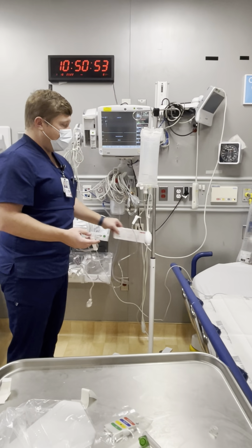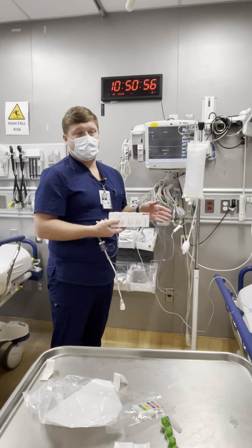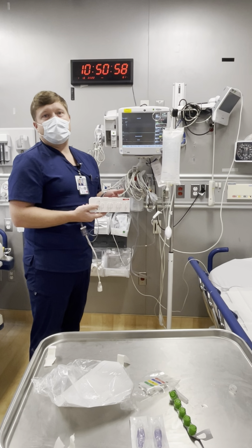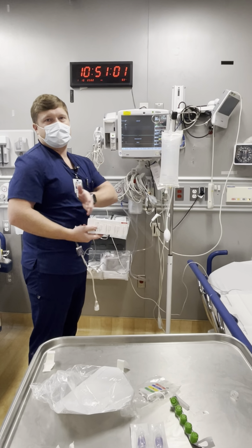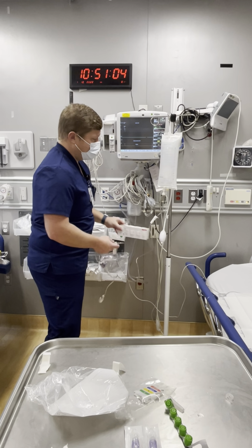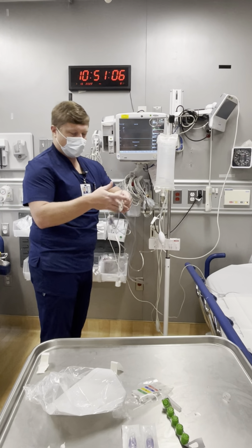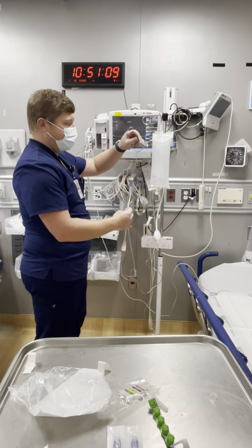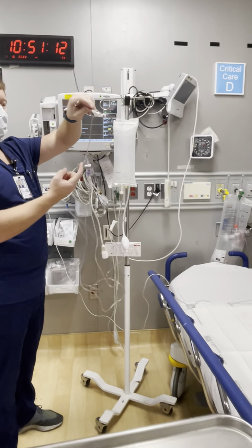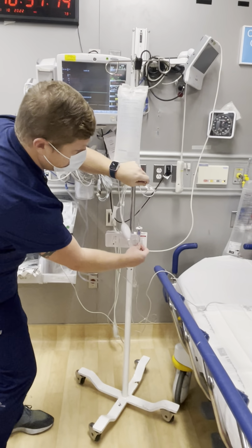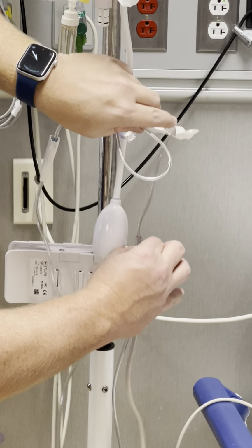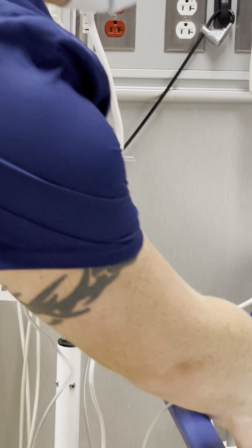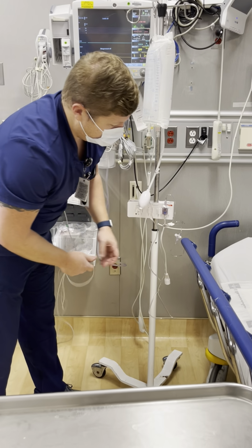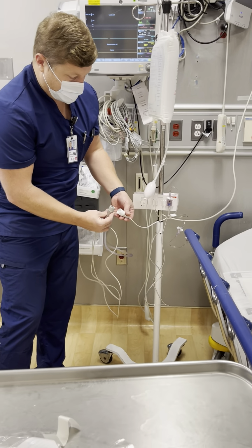All right, and typically we will have this transducer holder that will be available at the bedside or on a pole. If not, you just have to make sure you can actually tape it in emergencies to the apex as well. So the transducer will slip right in. The cable will go down. The one going to the patient needs to be pointing up. So it slides right in. It clicks. So what we're going to be doing while the provider is doing their portion is we are going to be finding the cable that connects to this transducer. It slides right in.